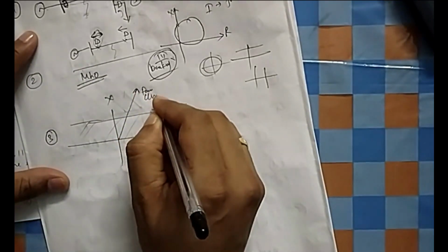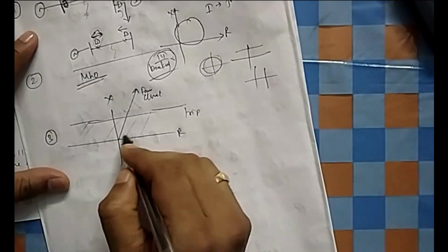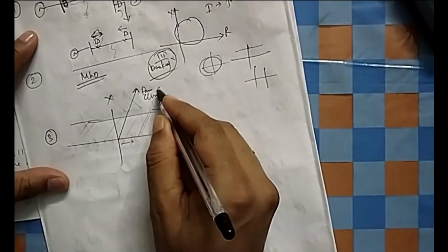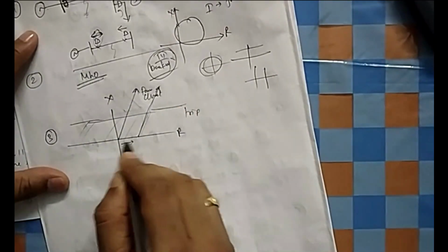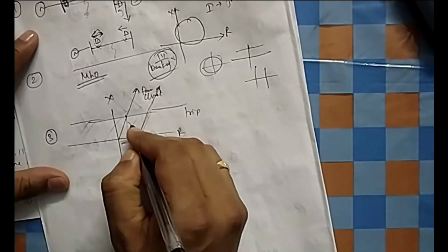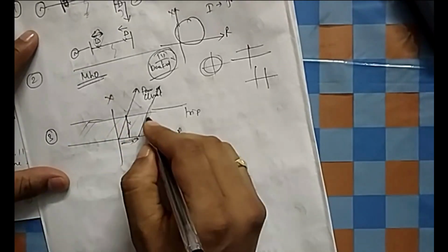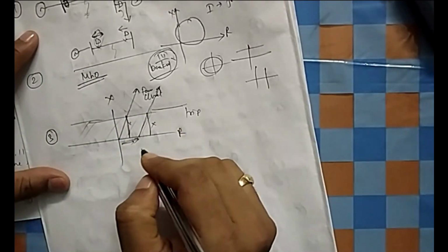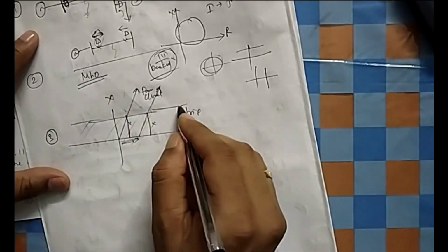This was the fault characteristic. Now if you add R, this fault characteristic will move to this side, because you are adding R. Suppose this was the X you are protecting of the line. That remains the same, so because X remains the same, it will still trip.